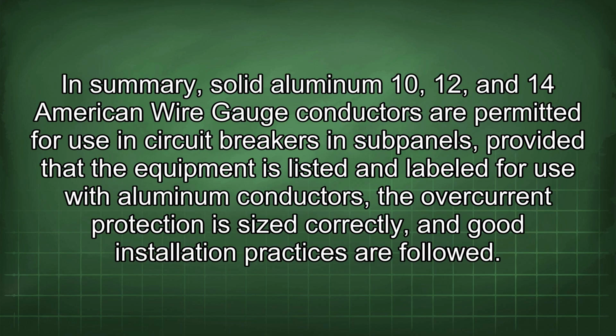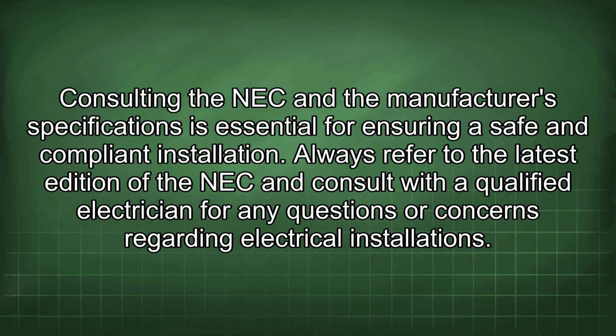In summary, solid aluminum 10, 12, and 14 American wire gauge conductors are permitted for use in circuit breakers and subpanels, provided that the equipment is listed and labeled for use with aluminum conductors, the overcurrent protection is sized correctly, and good installation practices are followed. Consulting the NEC and the manufacturer's specifications is essential for ensuring a safe and compliant installation.